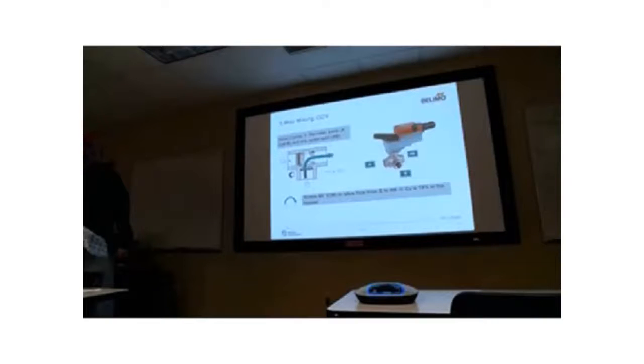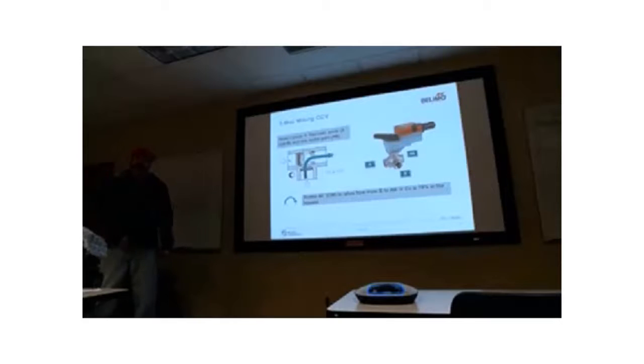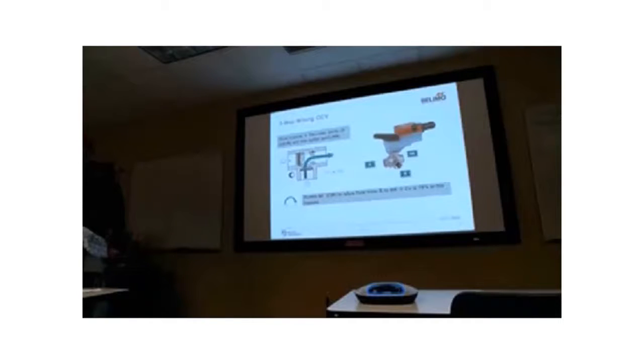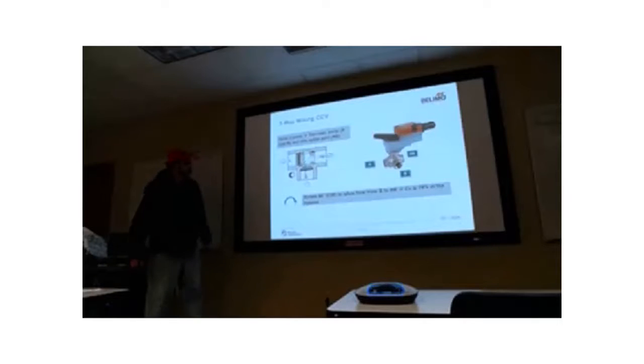Because what will happen is I had one of my customers spend almost 5 hours troubleshooting. What was happening is they had the valves in wrong. The chiller was tripping off on low flow, right? Because it wasn't getting enough flow back. And they beat their heads against the wall trying to figure out what was going on. And finally someone said, hey, wait a minute, this valve's in the wrong position. You could be a hero one day if you remember that.